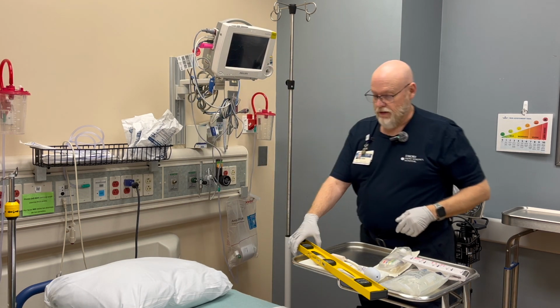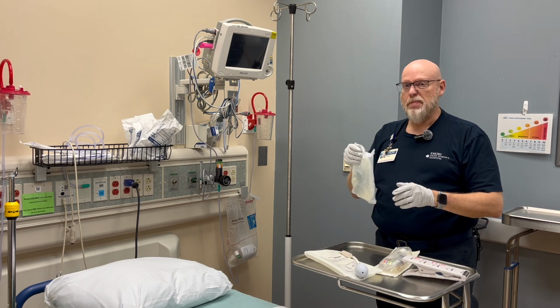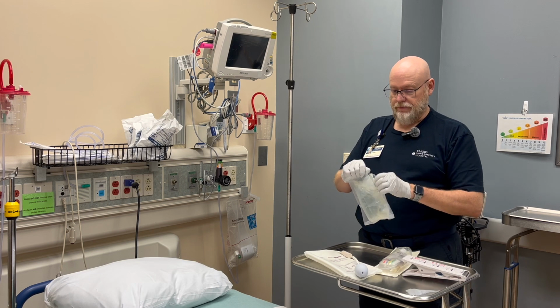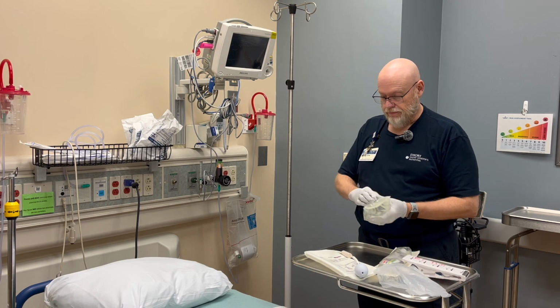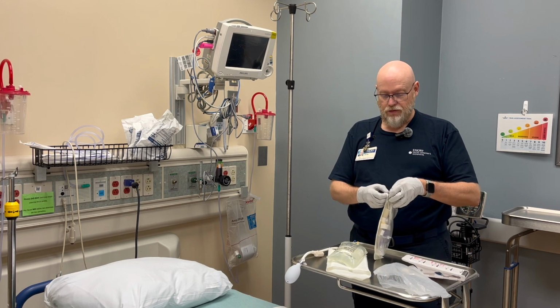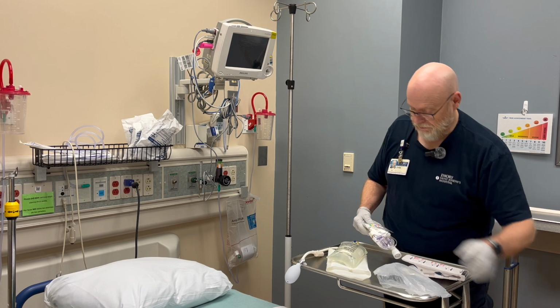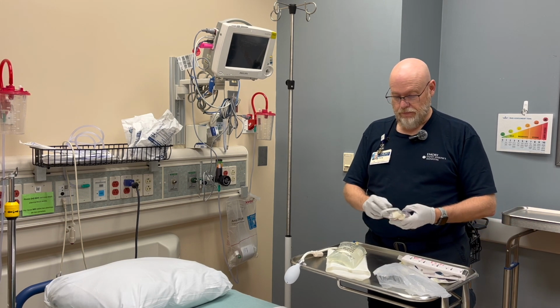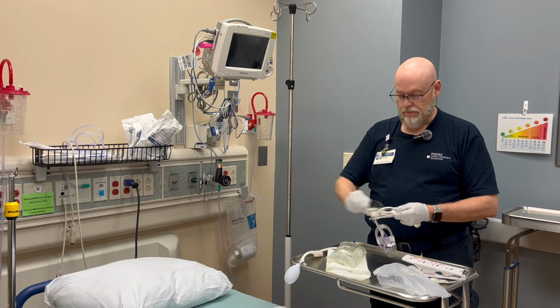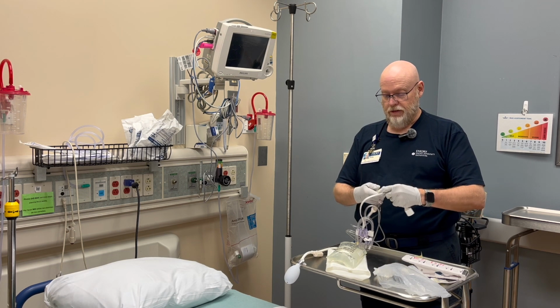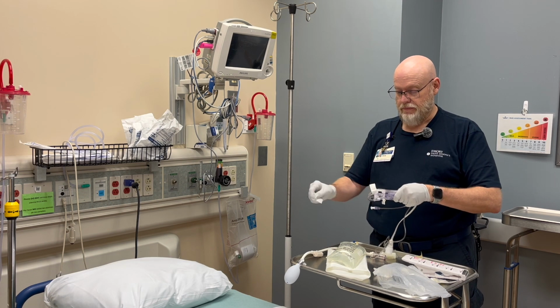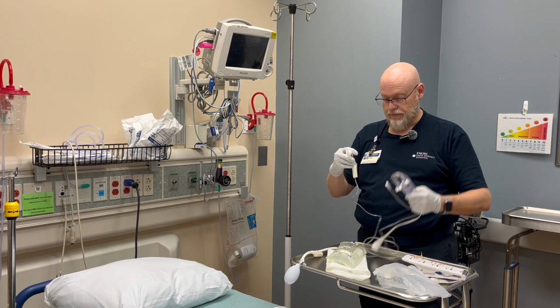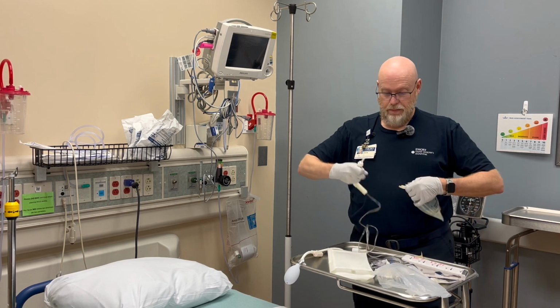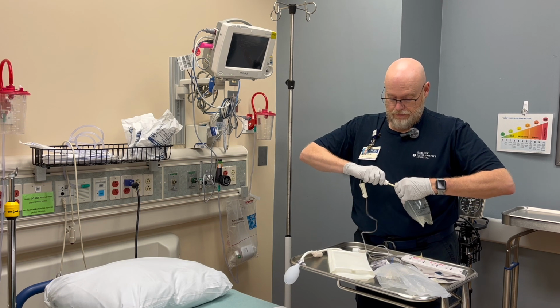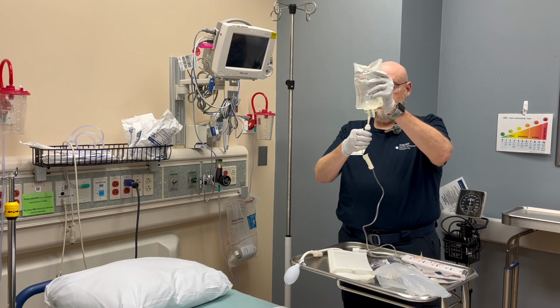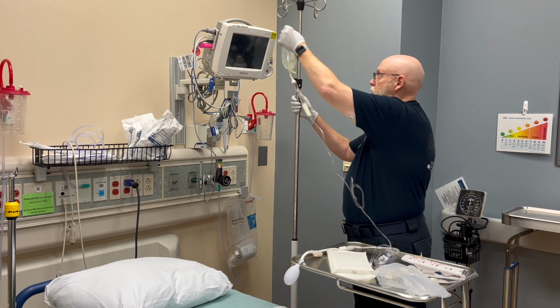port is. Okay, next thing I'm going to do is I'm going to spike my bag of saline. This is the transducer's tubing, special tubing. Now make sure that your roll clamp is clamped off. Okay. I'm going to spike the bag just like you normally would. Fill up the drip chamber. Hang it on the IV pole.